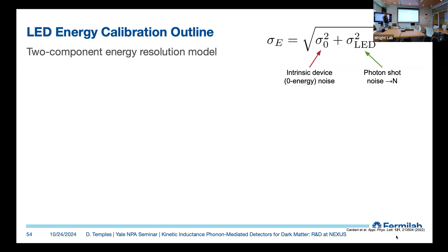All right, so we do the correlated noise removal. Then we look at all of the pulse windows from our pulse time stream, and we do some quality cuts to remove windows where there is spurious baseline noise or pulses that are not associated with an LED pulse. We then run an optimal filter-based pulse amplitude estimation in the frequency domain on each pulse window. And in this case, we're using, again, the average pulse as our signal template, not some analytical form. So we measure directly what our pulse shapes are and use those as our signal template. For each window, then, that looks something like this.